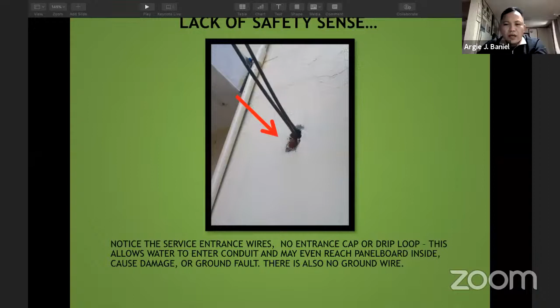And what happens in that conduit is there is a possibility that the insulation will break down, or if left for a long time, it shortens the life of the insulation, and it deteriorates inside the wire when water gets in. Lack of safety sense. Notice the service entrance wire has no entrance cap or drip loop. This allows water to enter the conduit, and may even reach the panel board inside, causing damage or ground fault. There are also no ground wires.